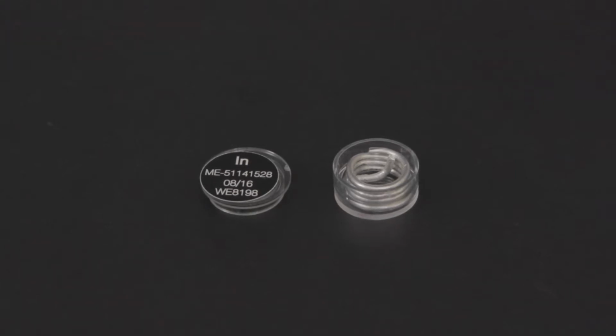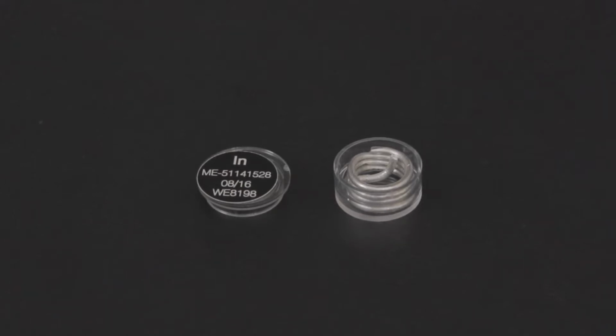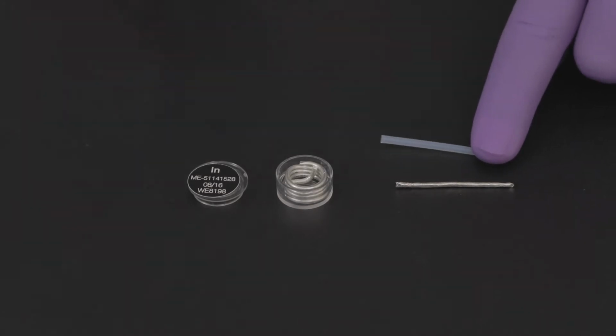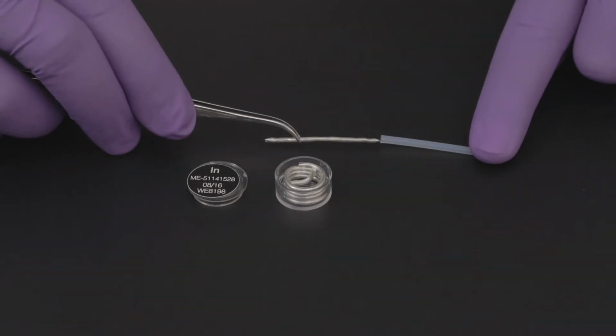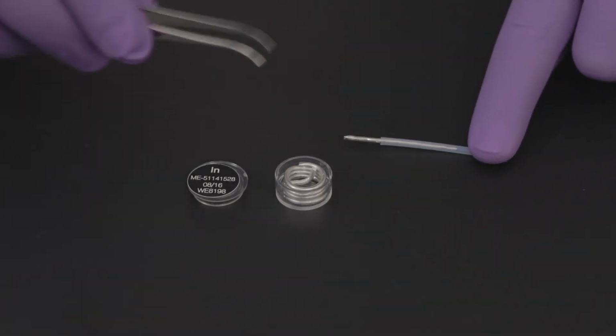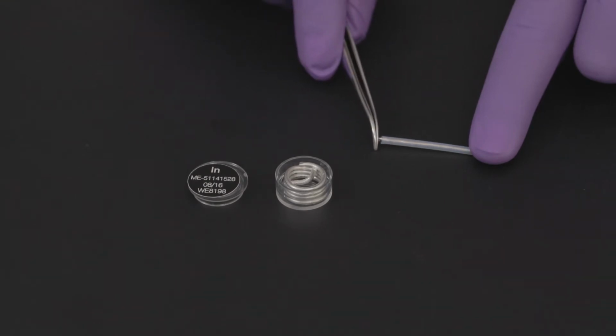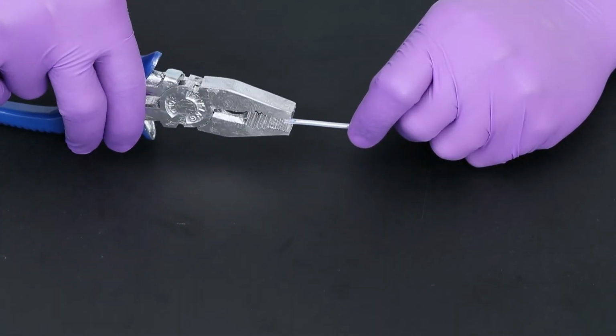The indium reference sample is measured, and the temperature of the fusion point is determined by the onset of the step on the storage modulus curve in the evaluation window of STAR-E software. Prepare a sample by placing a piece of indium wire in the supplied PTFE tube. Crimp the ends of the tube.